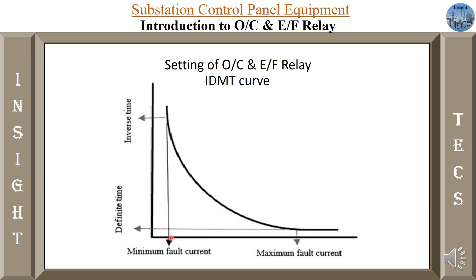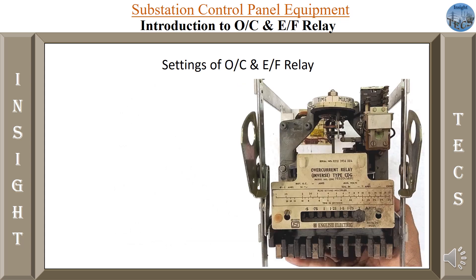When the current is minimum, the relay will give some time for fault clearing — it allows time for the fault to clear itself. If it is a high current surge, it may be a mal-operation if it operates instantly. So it gives some definite time for the relay to operate. When minimum fault current flows, more time is required; when maximum fault current flows, the time to operate will be less. Based on this concept, the settings of over current and earth fault relay are done.